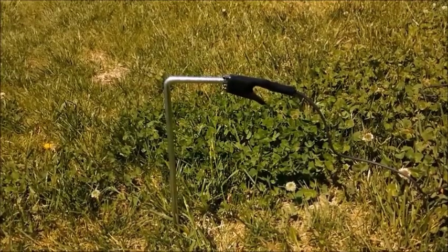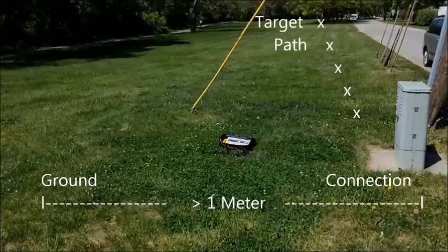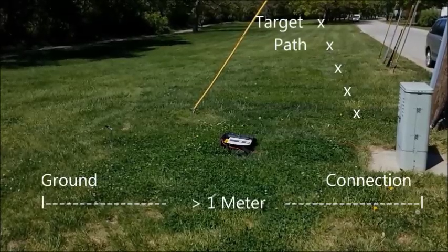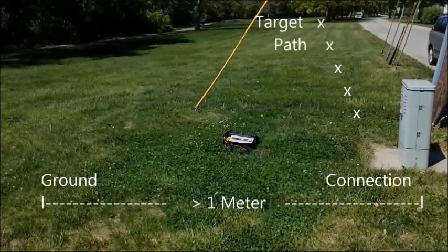Connect the black clip to an independent ground rod placed at least one meter from the connection point and at a 90 degree angle to the path of the target conductor.